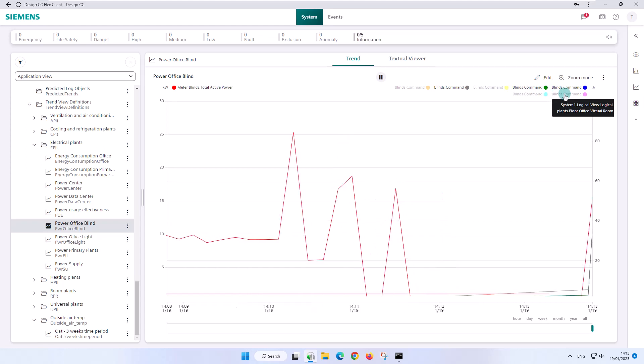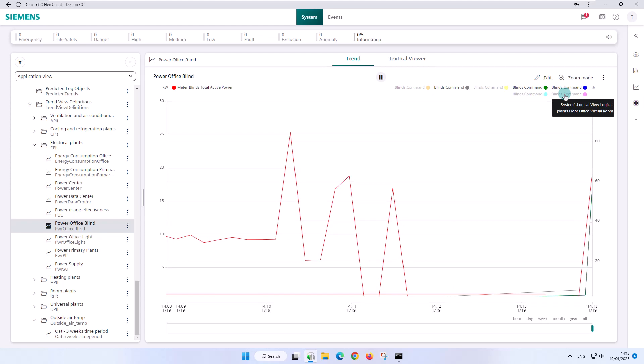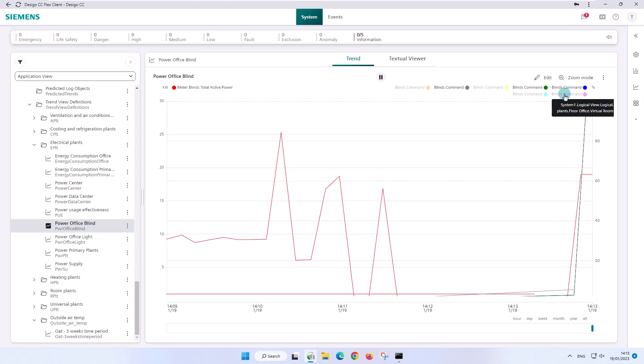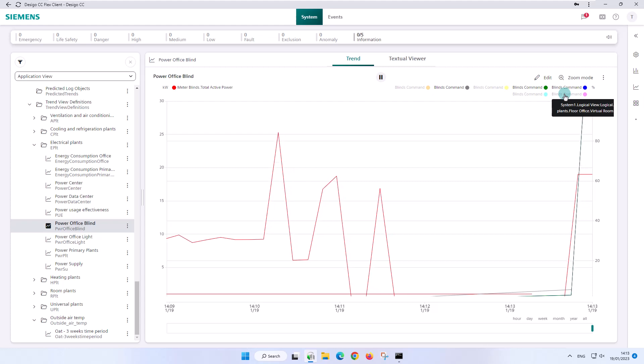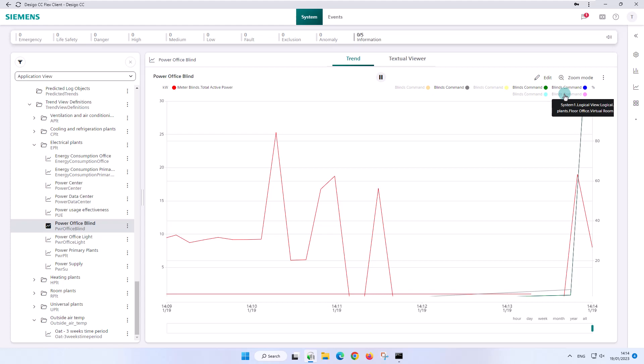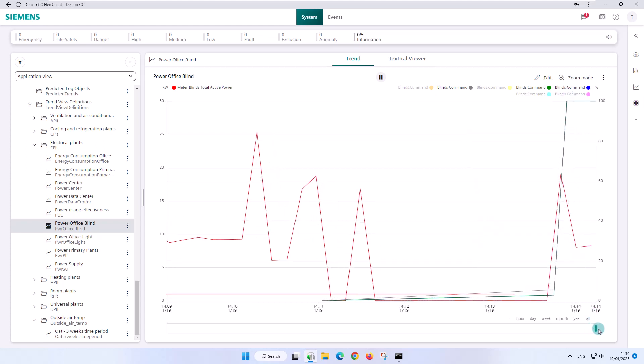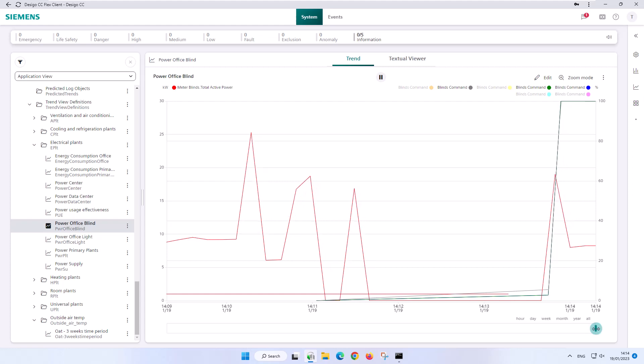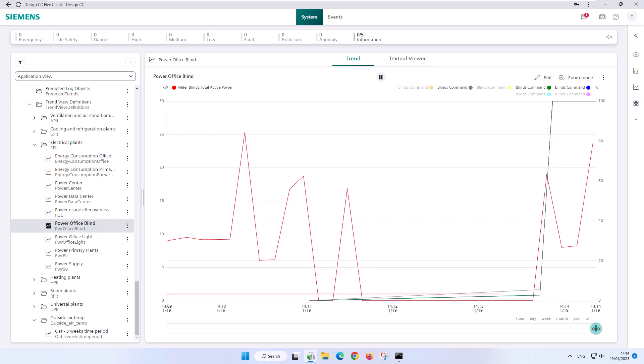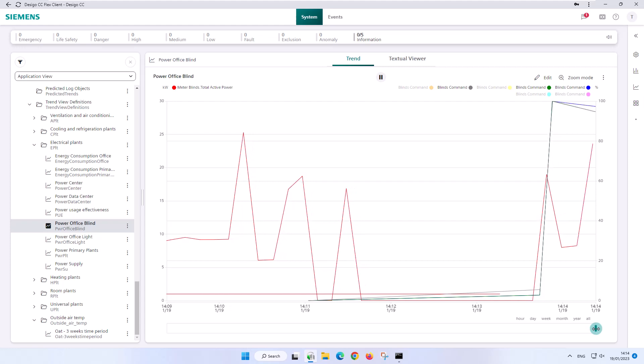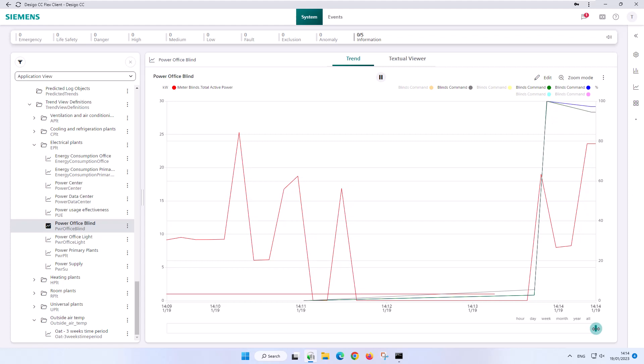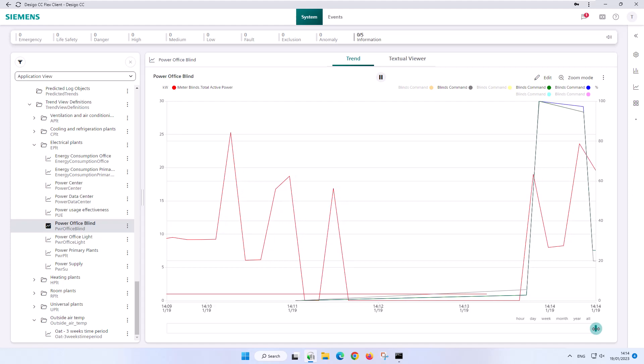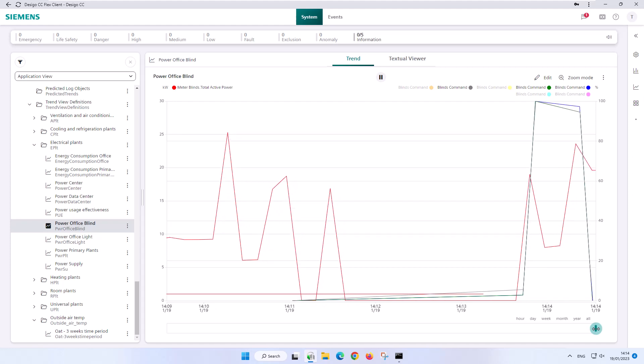The trend series in the database of Desigo CC of the various trend objects are always updated by default in the open trend view. In the case of online trends, this is done continuously, as is clearly visible here with the type of trend view definition we are currently using. With the selected time period in this chart, the updating is done in very short time intervals. For the offline trends, this usually happens automatically when the notification threshold of the trend log object is reached, which is undefined in time. We are still in the process of analyzing and investigating and would like to show you a few more tools that are helpful and efficient.